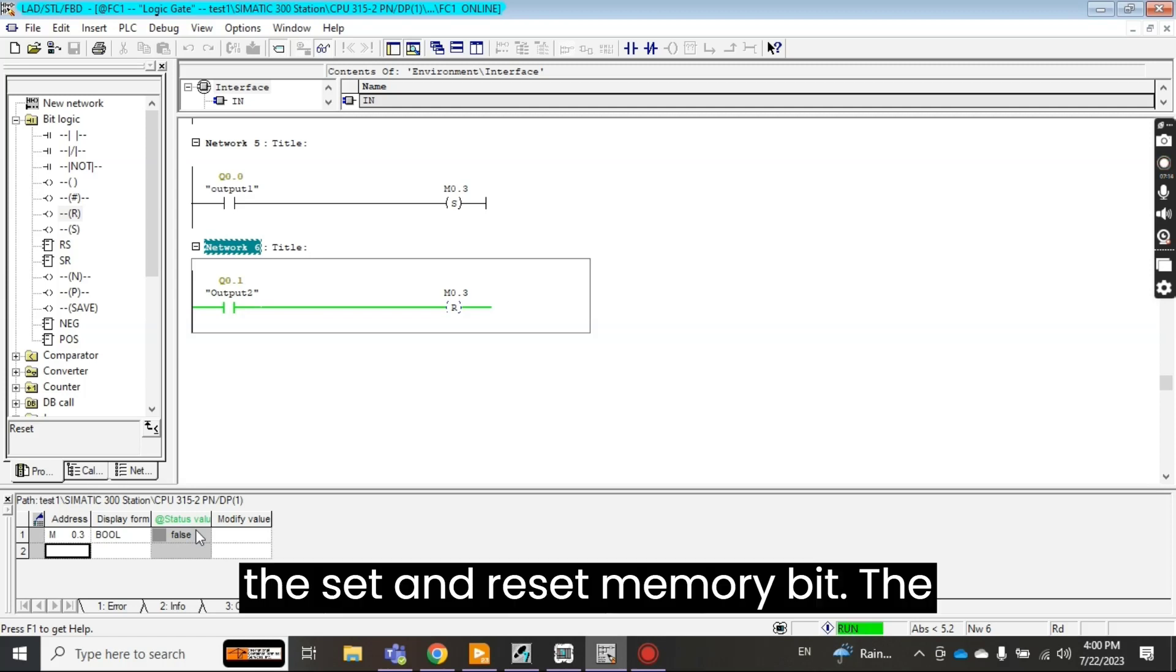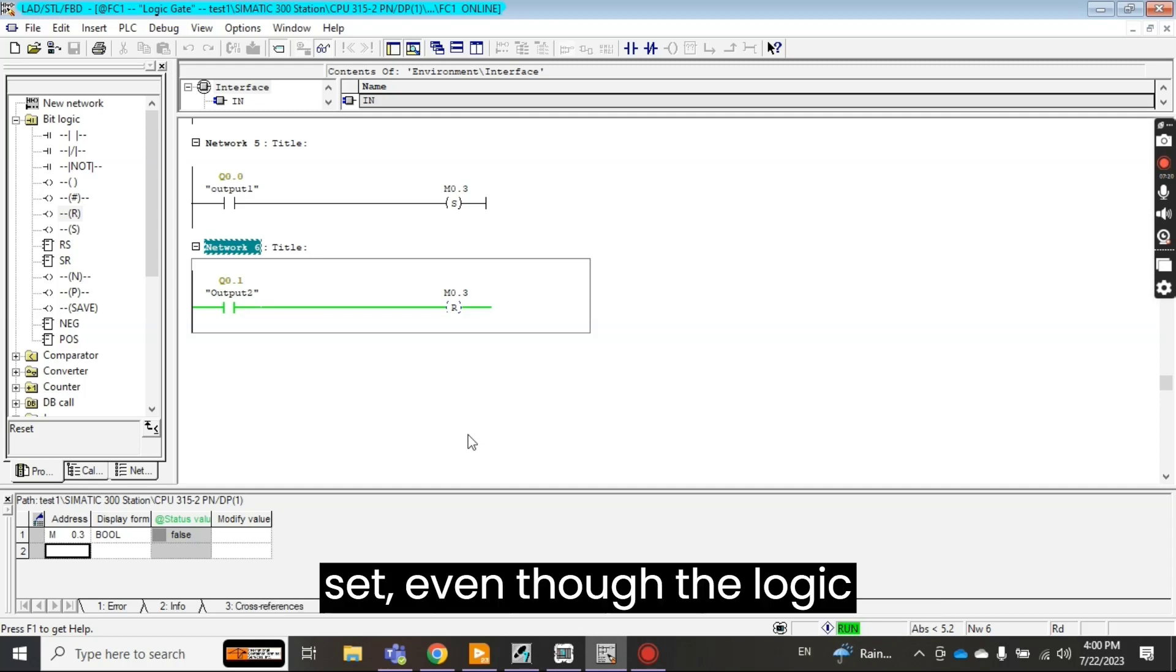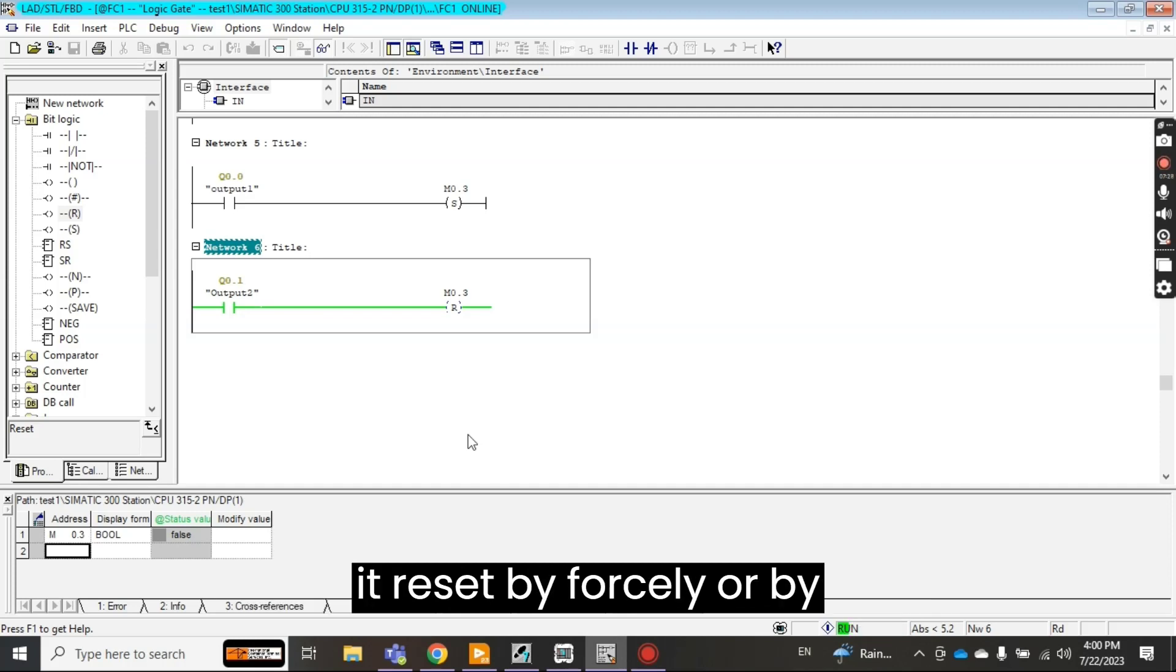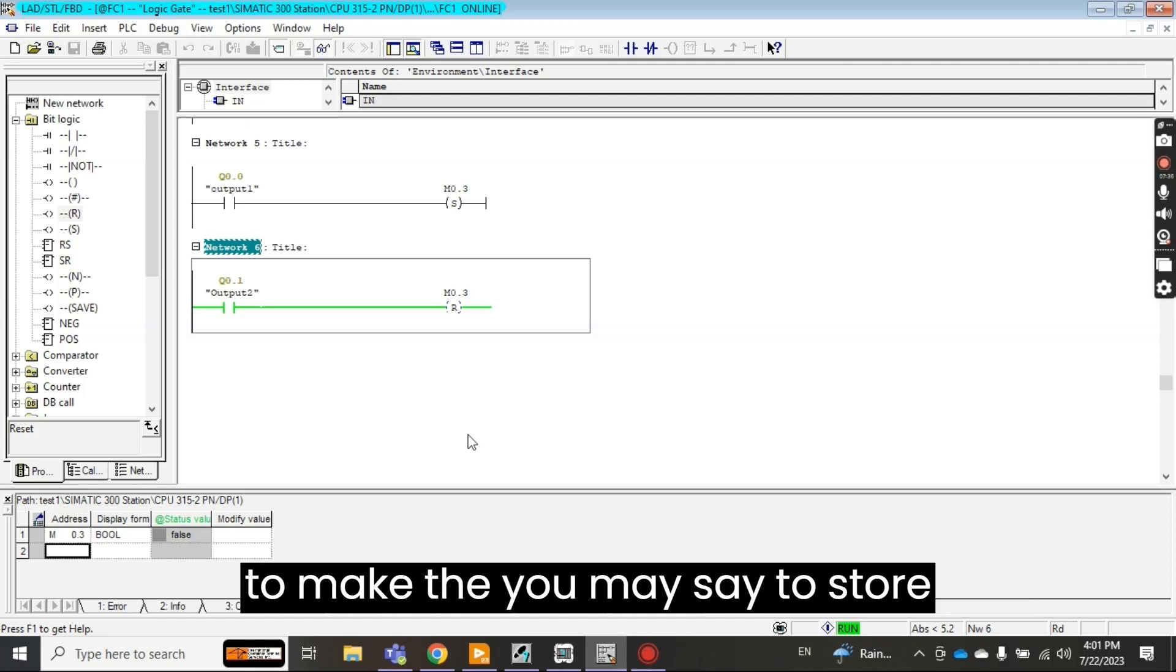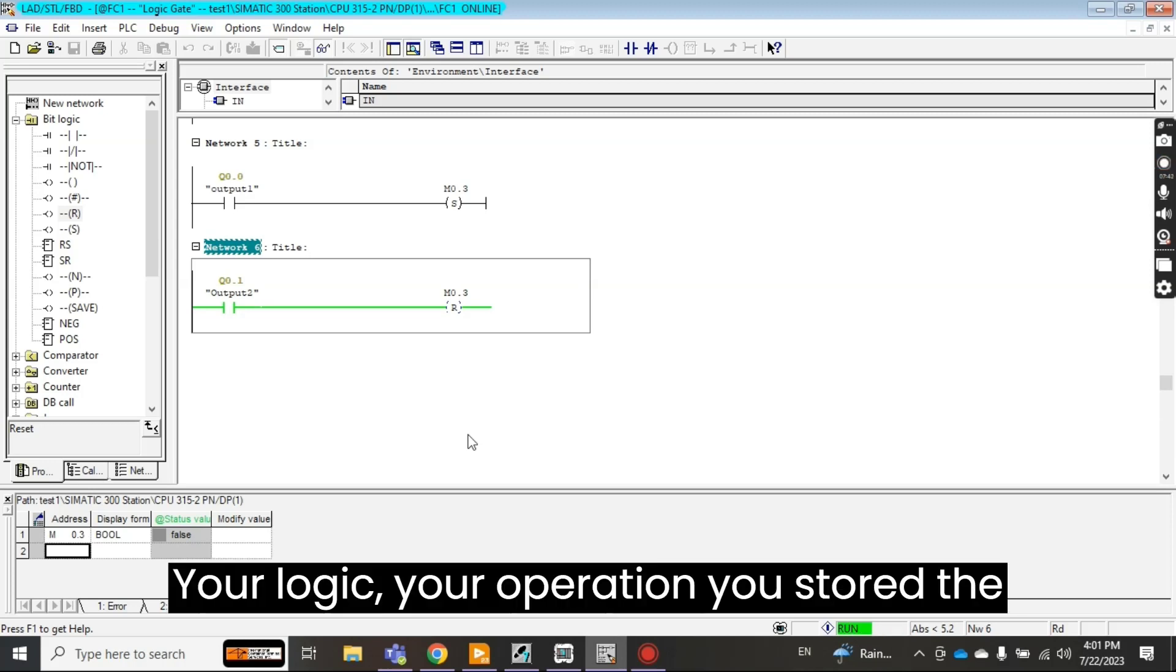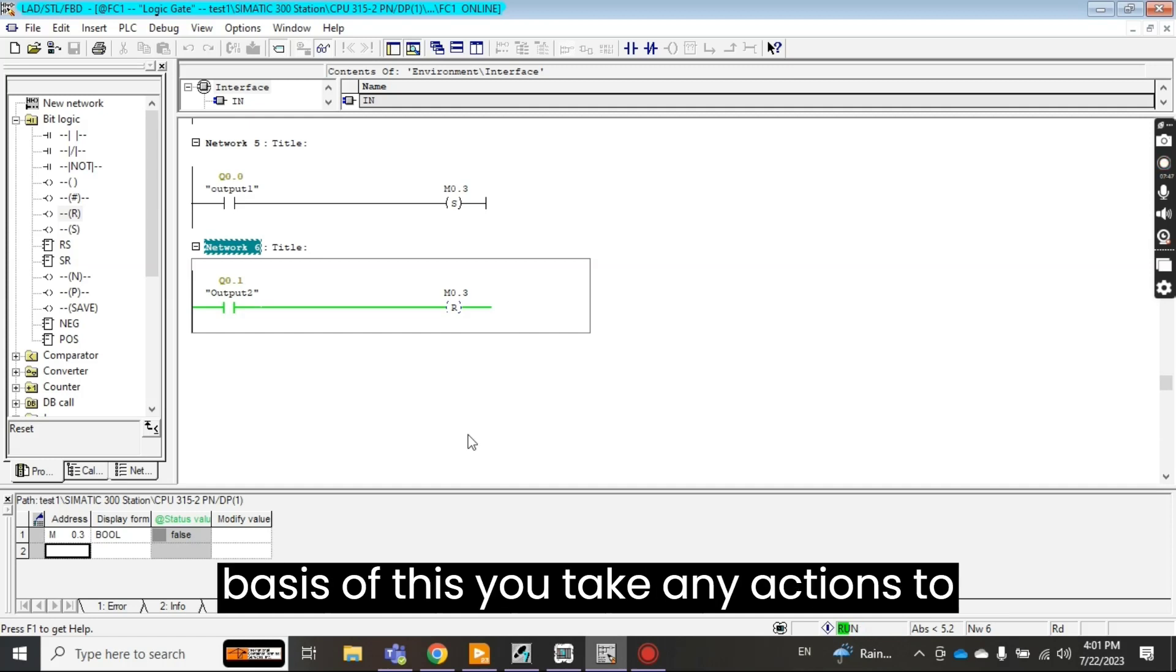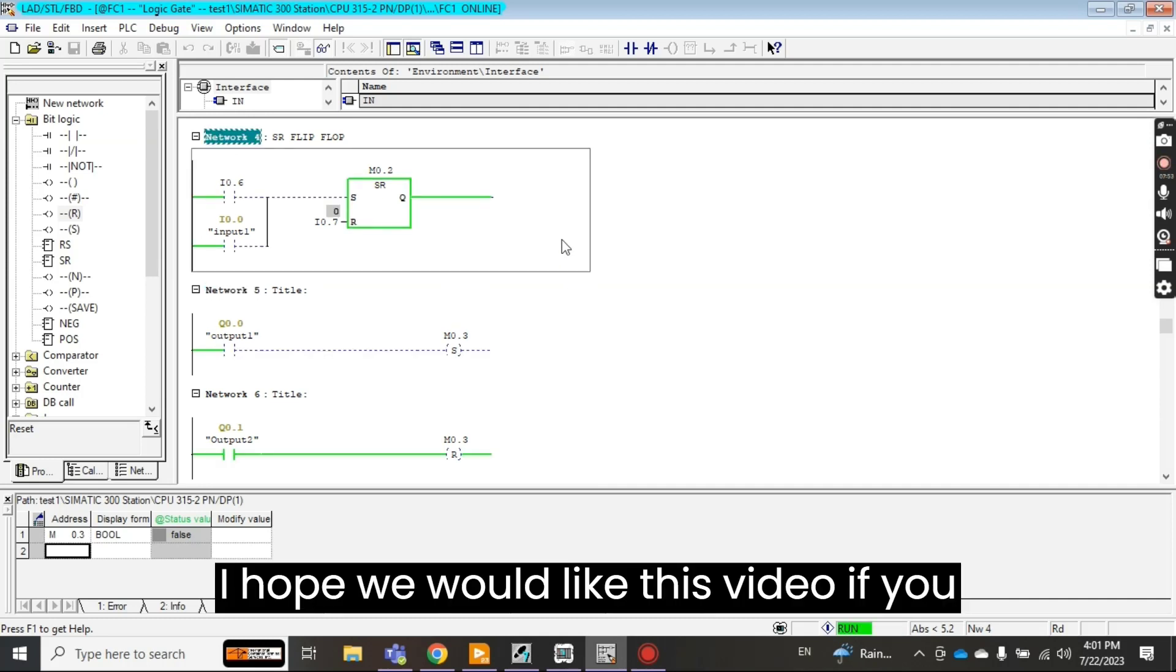So the set and reset memory bit, the advantage of is that once it is set, even though the logic behind is false, it will remain set unless you make it reset by any logic. Then it will be reset. So it's very important use in the programming to store the status of your logic, your operation. You store the last status. And then on the basis of this you take any actions to perform the operation.